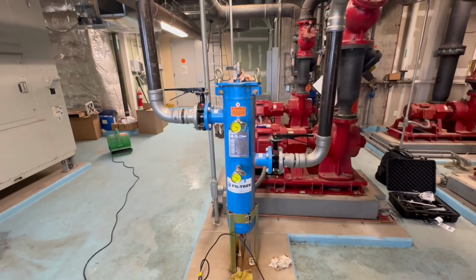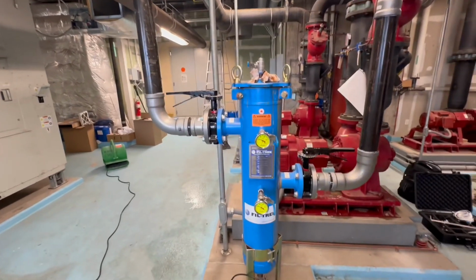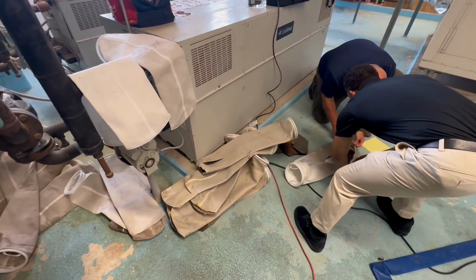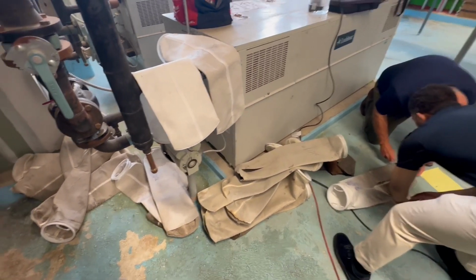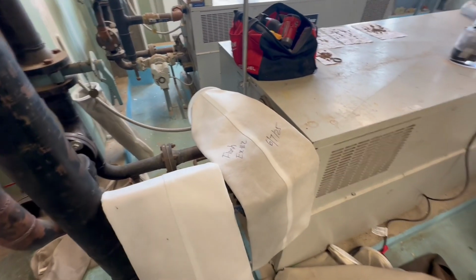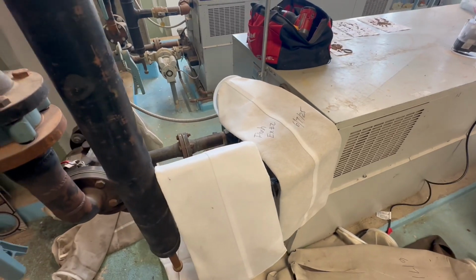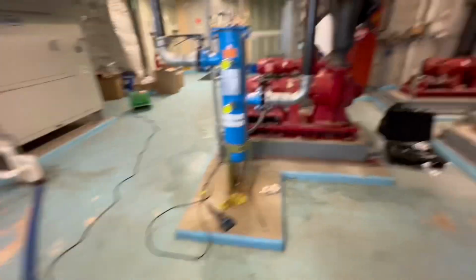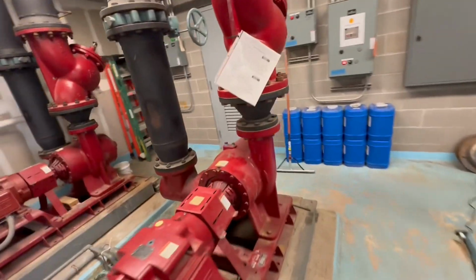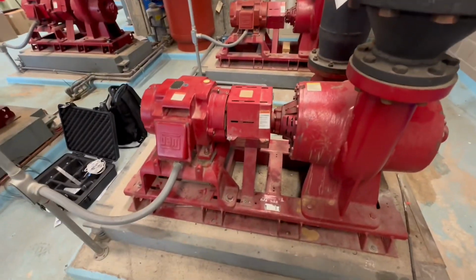We've also added a bag filter. This is a Fil-Trek carbon steel bag filter running a 10 micron bag filter. And the customer has been changing the bags every week or so. We've collected some samples of that to be analyzed. But essentially the way this system works is we work off of the differential pressure between the suction and the discharge of these main condenser water pumps.